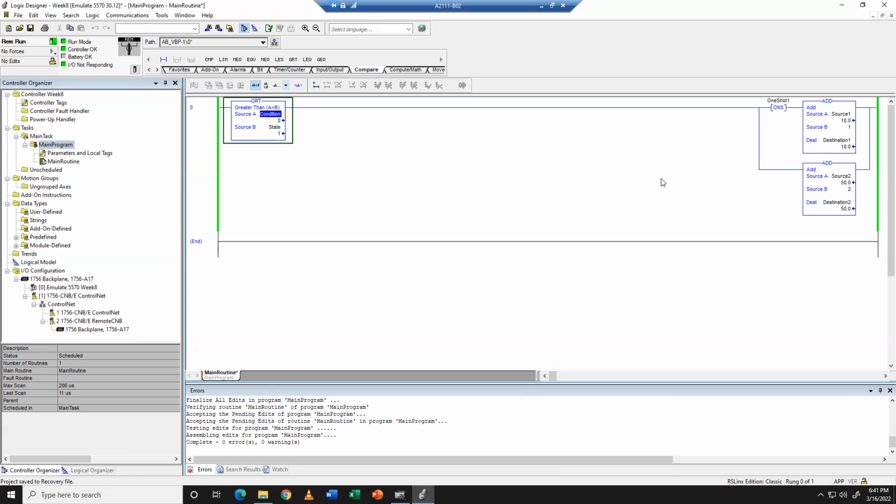The math isn't perfect and it's very dependent on the sample rate of the PLC, but there are other flow meters that will work on pulses. So when the flow meter itself calculates that 100 liters has gone by, you'll get 1 pulse, and then you can add 100 liters or whatever to your signal. Maybe that pulse might stay on a while. There could be a latency to it. So instead, let's say, well, we have a condition that becomes true.